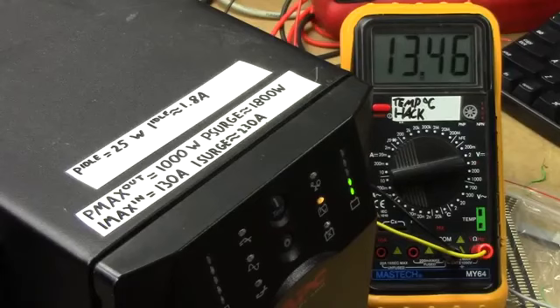Now, making an inverter out of an old UPS is hardly anything new. Lots of people have done it in the past, and it's basically just a question of beefing everything up a bit and adding a bit more cooling. But anyone familiar with the smart UPS range is going to have a bit of a head scratcher, because these are natively 24 volt units, and if you hook a single 12 volt battery up to them, they simply will not do anything at all. They'll just sit there as if no battery was connected at all.